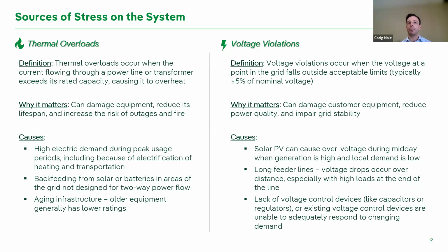These can also damage equipment and impair the stability of the grid. Again, these happen because of the solar interconnected to the system, and when we have a very long span without voltage control devices on them, we also see the voltage drop or increase.